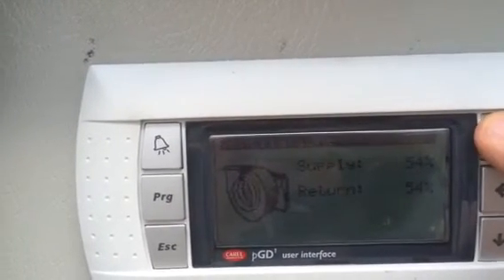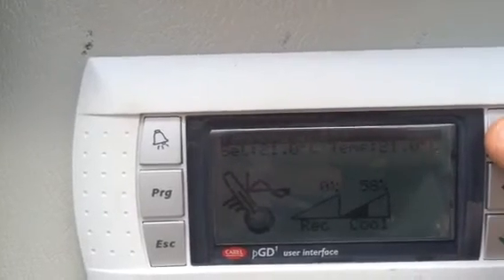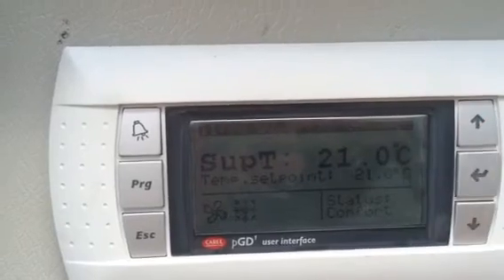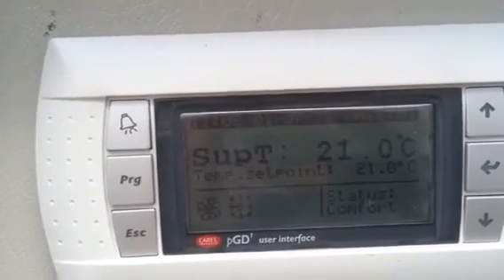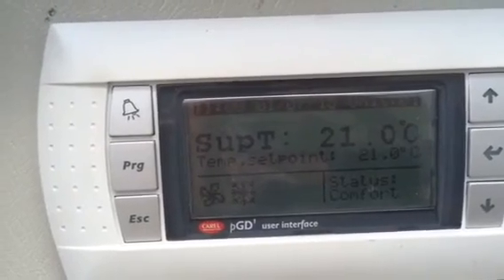Discharge temperature is 52 degrees, the fans are running at 54% of their capacity, and cooling demand is at 58%. I'm back to stably controlling plus or minus two degrees above and below set point.